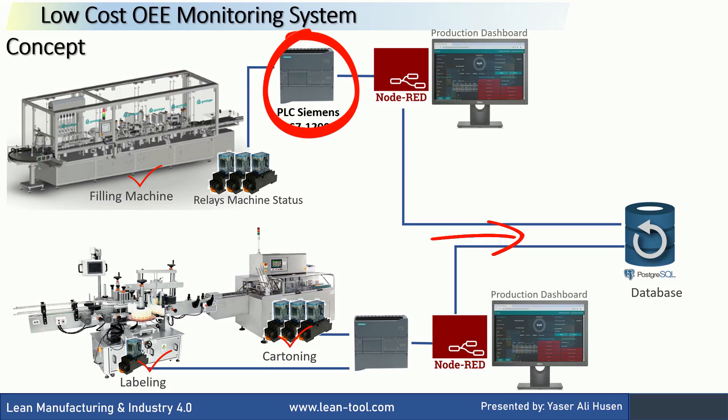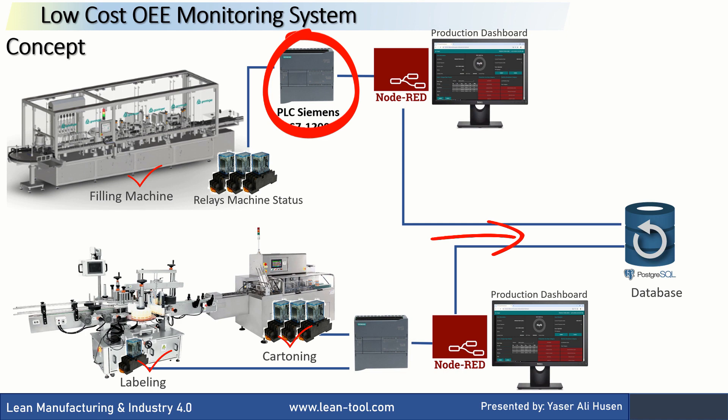Node-RED then records the data into the database according to the signal conditions received from the relays. Node-RED in the production line also has a dashboard used by operators to input their IDs, change the running product, input defects, select the stop category during downtime, and monitor the OEE value in real time.